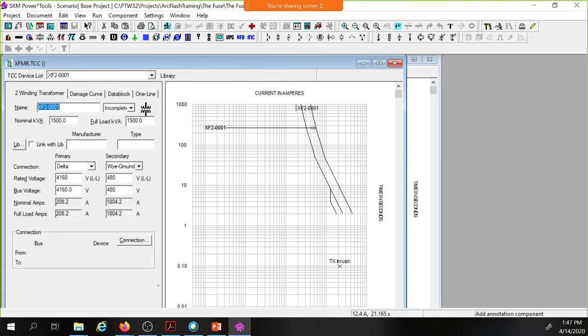Let's see, I need my calculator. Anybody out there want to hazard a guess for a primary fuse size? What would you pick? So I have 1500 kVA. Divide that by 4.16, divide that by 3, multiply that by the square root of 3. That's 208 amps on the primary. Sound about right?